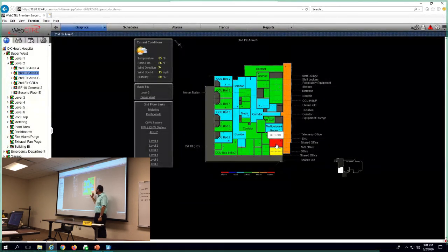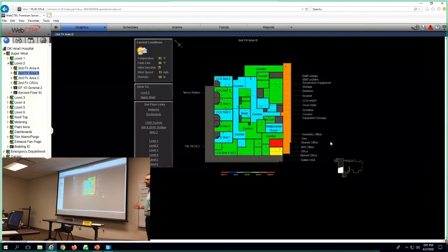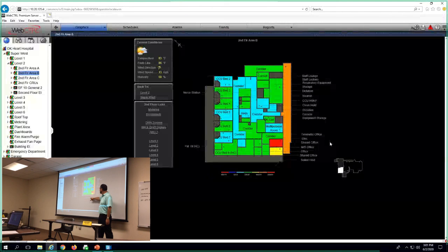So I'll tell you right now, if I look at this floor plan, the south half of the second floor, the whole floor is good except for these two zones. Something is wrong in this space because it's in the red. It's in alarm. This is probably 3 or 4 degrees off the set point, or maybe 4 or more. The orange is probably 3 degrees or above that set point.